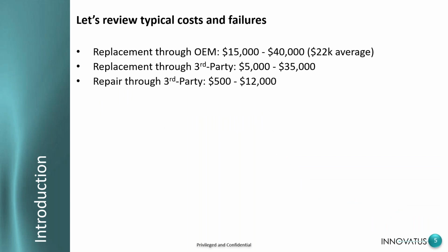So typical costs and failures for an average TE probe, I guess we'll call it. Replacement through the OEM is $15,000 to $40,000, and I've seen some of these higher end TE probes go up to $60,000, so that average is actually higher than the 22 we have on the slide. Replacement through a third party can be anywhere from $5,000 to $35,000 if you're just buying it. You know, you're letting your fingers do the walking. You're calling your third party providers. You're just shopping around online. But repair through third party is anywhere from $500 to $12,000 or so. And the beauty about repair is using the proper materials, processes, procedures and testing, we can restore those probes back to OEM form, fit, and function and provide a warranty that's equal to or perhaps even longer than a brand new one from the manufacturer.